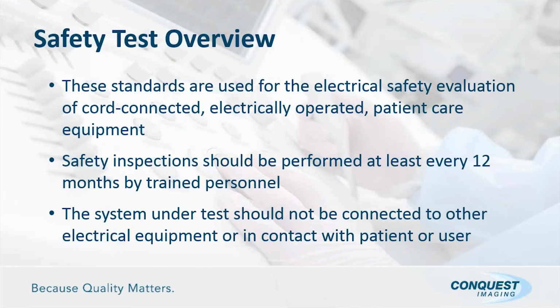We want to talk about some safety considerations. The standards are used for the electrical safety evaluation of cord-connected, electrically operated patient care equipment, and that's exactly what we're talking about when we talk ultrasound. Safety inspections should be performed at least every 12 months by trained personnel. Now it's important to understand that even though NFPA 99 says at least every 12 months, there may be accreditations out there, such as American College of Radiology, that require these safety inspections be done more often.